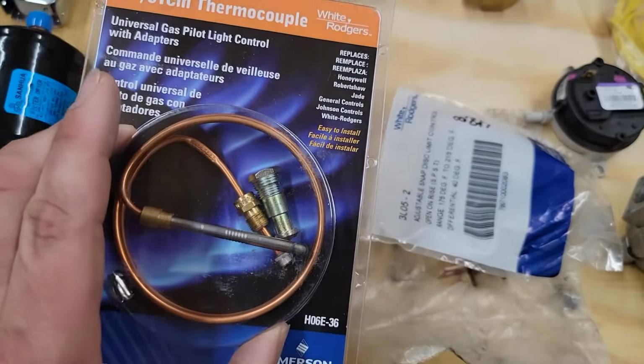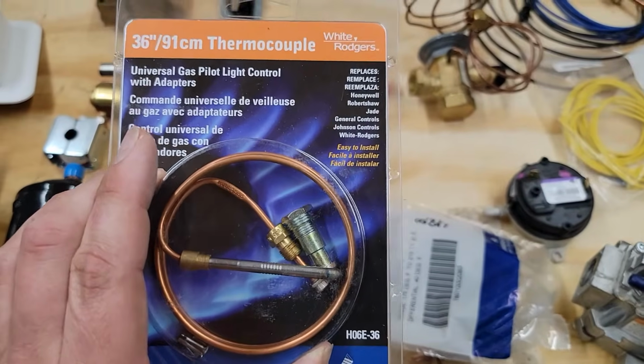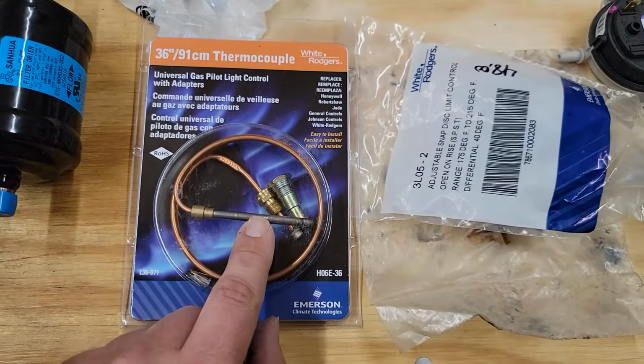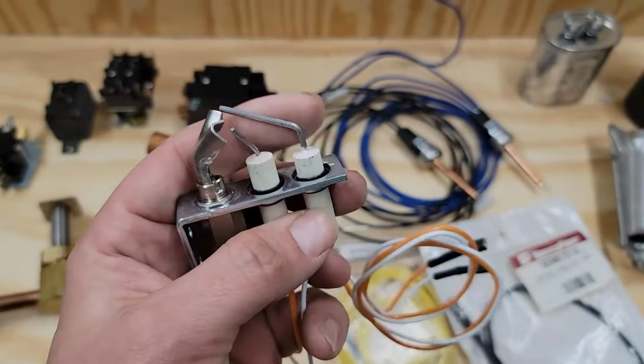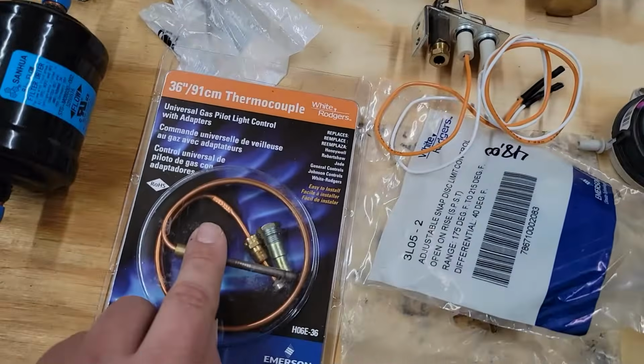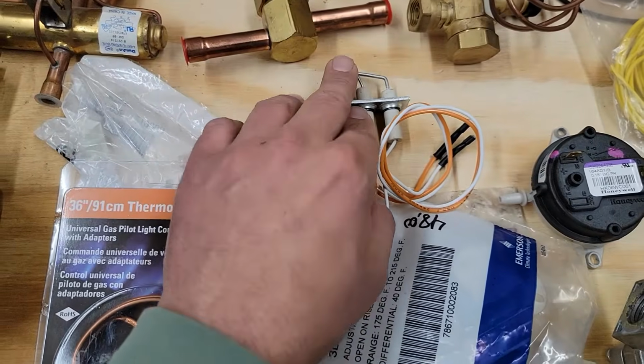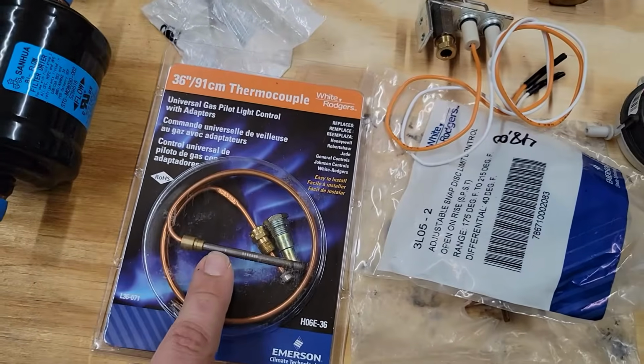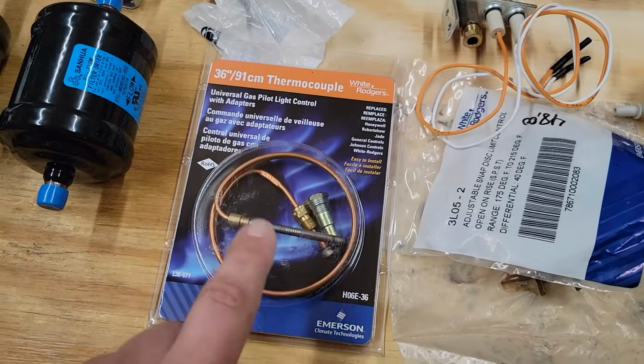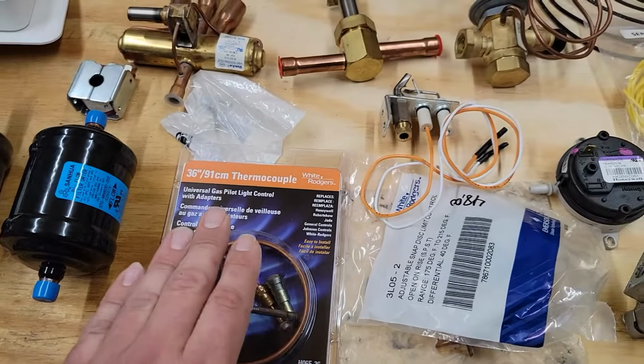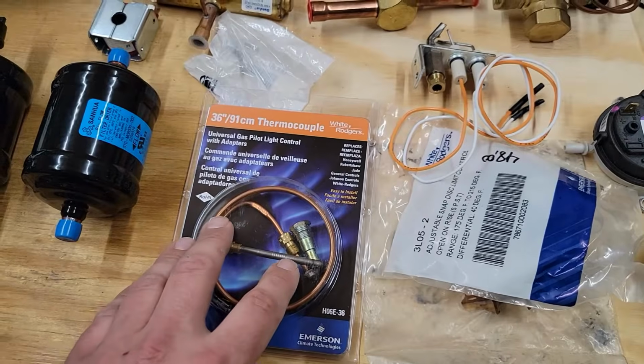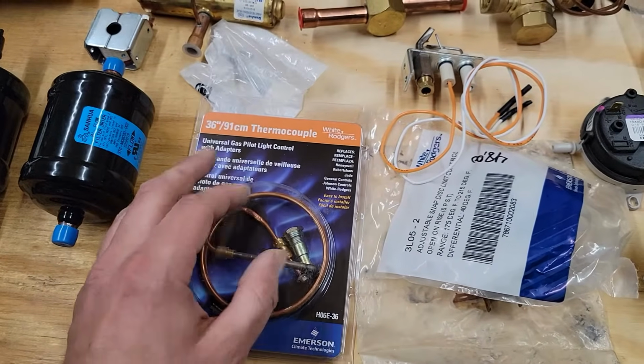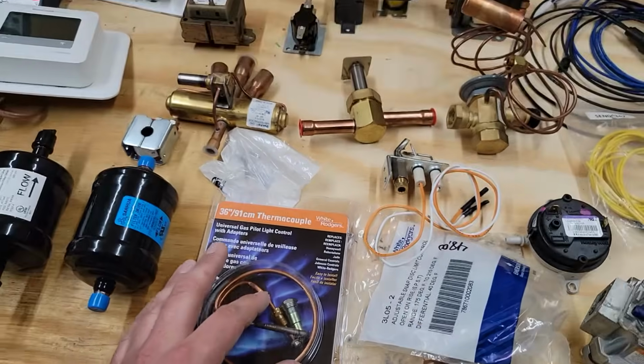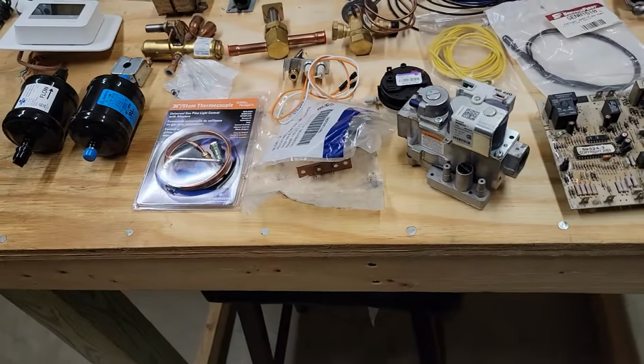This right here is your thermocouple, and this is on standing pilot systems, and this right here is in front of the flame. Let's see, just like this right here. See this flame sensor? That's basically what this thermocouple is, and it would be right there, and whenever your pilot would light, then this right here senses the flame and sends a signal back to the gas valve, letting the gas valve know that, hey, we have a signal, we have flame presence. And whenever there is no flame presence, then this millivolt signal would not be sent back to the board, and it would shut the unit off. So this is like a safety right here.